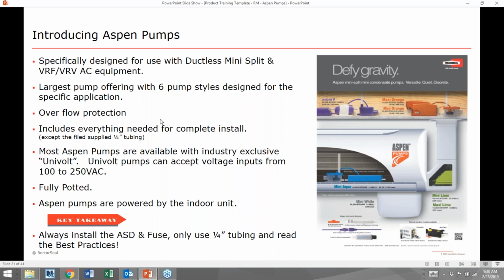All Aspen pumps include overflow protection that, when wired properly, if the pump is not capable of keeping up with the condensate being produced, the pump will shut the indoor unit down. Every Aspen pump includes everything needed for a complete install, whether it's Velcro tape to hold down the reservoir, screws to hold down the pump body itself to the wall, everything needed, with the exception of the discharge tubing, which is field supplied and is always 1/4-inch ID tubing.